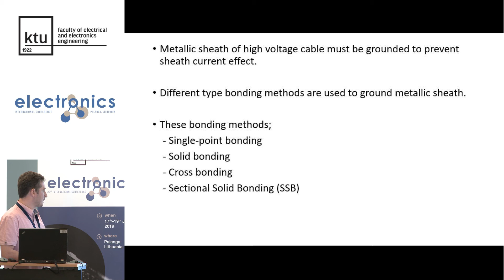Single point bonding is shown in this figure. If a single point bonding will be used, high voltage line length should be less than 200 meters. Otherwise, high voltage occurs end of high voltage cable line. Thus, solid bonding and cross bonding methods are used for long high voltage underground cable lines. Solid bonding, cross bonding are shown in figures. Solid bonding and cross bonding. However, sheath voltage SV of cross bonding method is generally more than solid bonding method and touch voltage limits. So solid bonding can be suggested for bonding of cable.